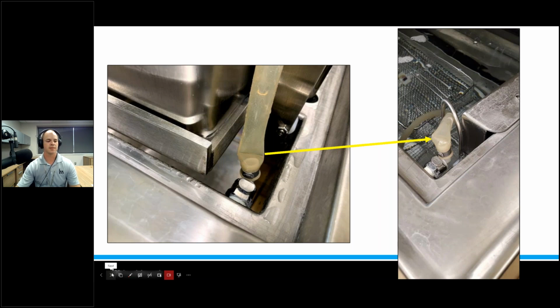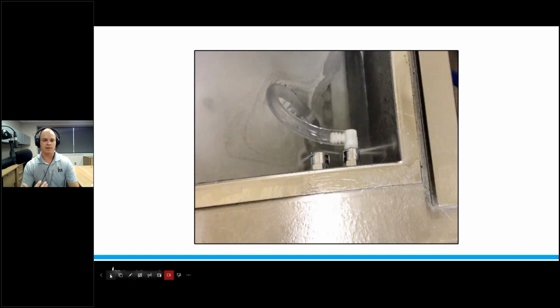So can the ultrasonic clean lumens if the flushing mechanism isn't used? All right, so I mentioned earlier, a lot of you either don't have ultrasonic cleaners that have the lumen cleaning function, and many of you out there have it, but whoever made the decision is not using the lumen cleaning function. So there's those two camps out there that maybe are wondering, after seeing this, will an ultrasonic cleaner really get in there and clean inside those lumens if it doesn't have that flushing or cleaning mechanism built in?